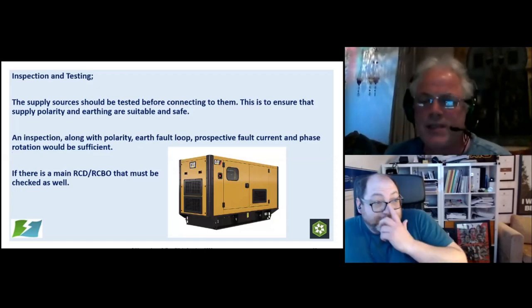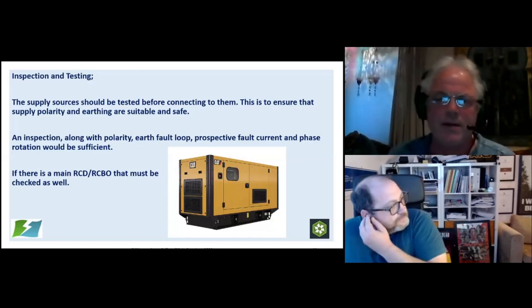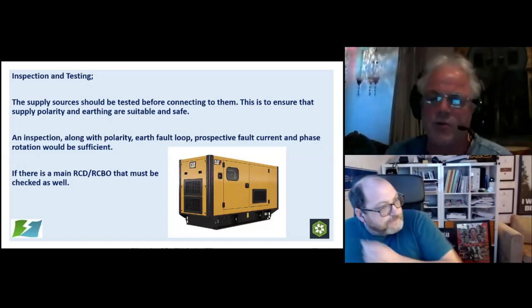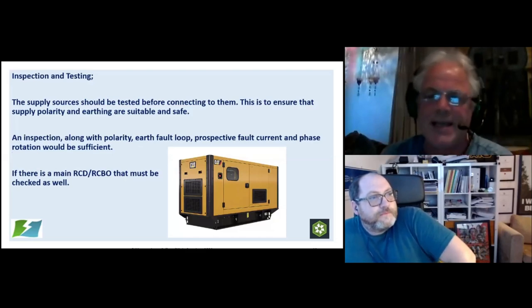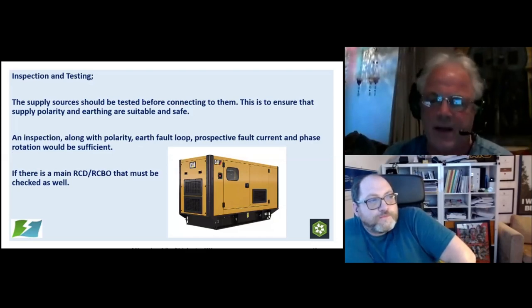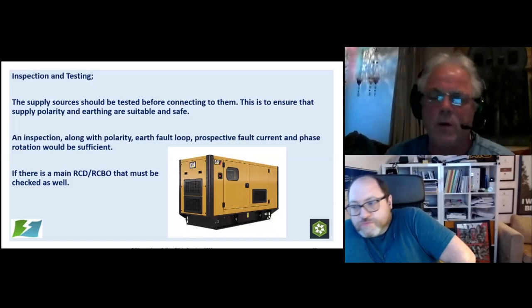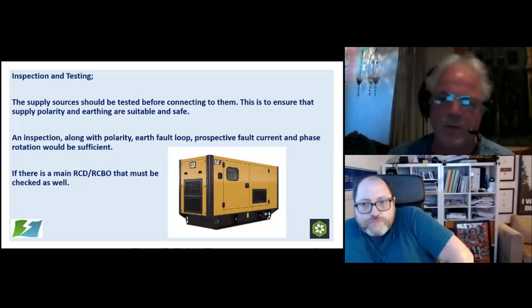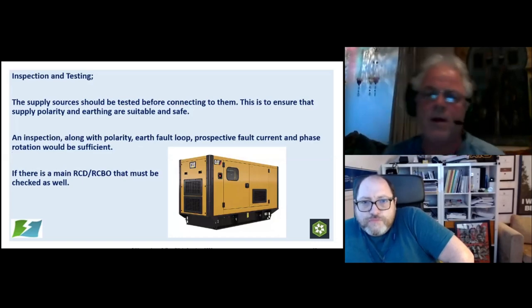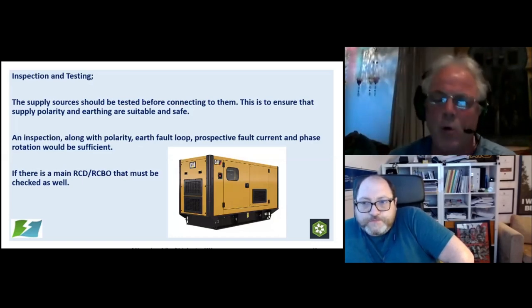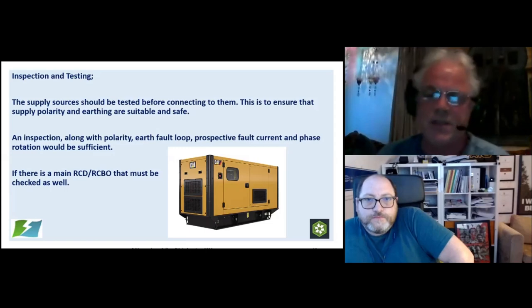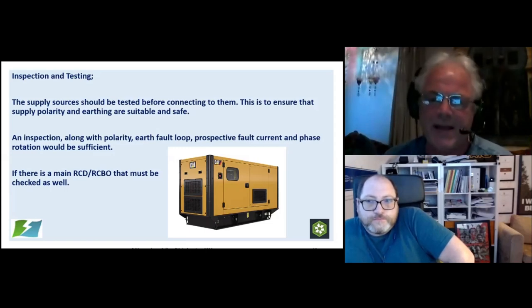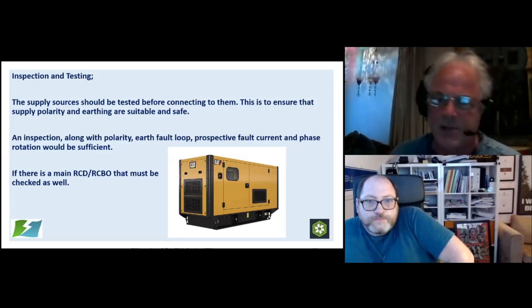So the supply sources, if you're going to plug into a source, a fixed installation source, if you're going to plug into anybody's socket outlet, you need to make sure it's safe before you plug into it. So generally we carry out an inspection along with looking at polarity, earth fault loop impedance, and checking the prospective fault current before we use it. Also check what the protective devices are behind it. Okay, if there's an RCD or an RCBO, that needs to be tested as well. Don't just go willy-nilly plugging into sockets.